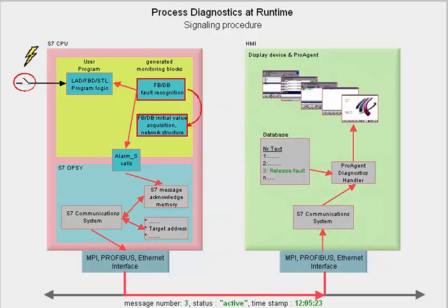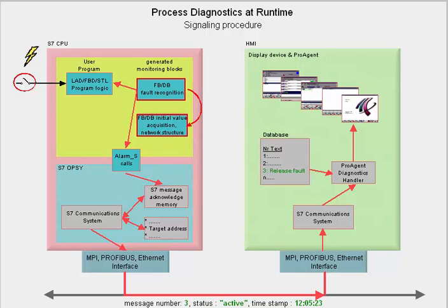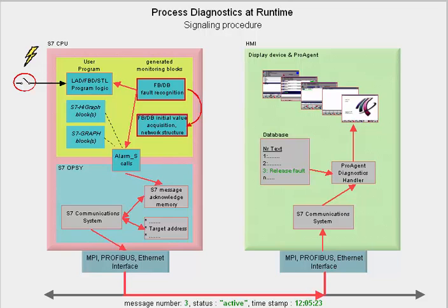Here we have shown you a run for the ladder, function block diagram or statement list language using S7 P-Diag. But the principle is identical with S7 Graph and S7 HiGraph. It is just that the monitoring process here is already an integral part of the language. This means that you do not need any explicit monitoring blocks here.